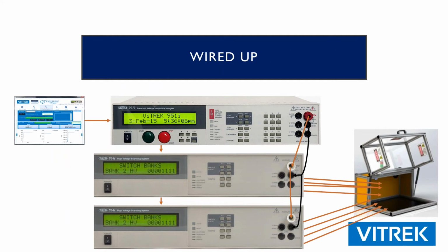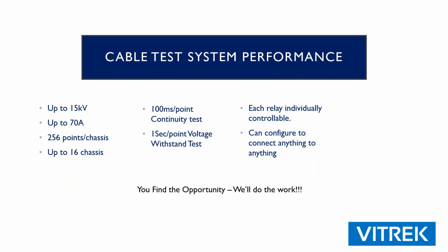Once we determine that, these units are going to get stacked together, sometimes in a rack, sometimes it's just a couple of units, with Quick Test Enterprise typically being the front end, and then your DUT might end up in a safety enclosure like that, and we're going to run some tests and create some data. So this is kind of where we talked about what we're looking to do here. Up to 15 kV is really the limit on that 964. We can go to 70 amps. 250 test points is pretty common, although we can go higher than that. Test speeds can be 100 milliseconds or even faster in some situations.